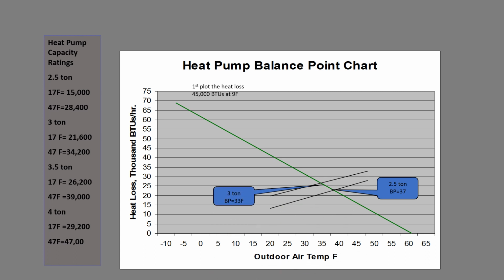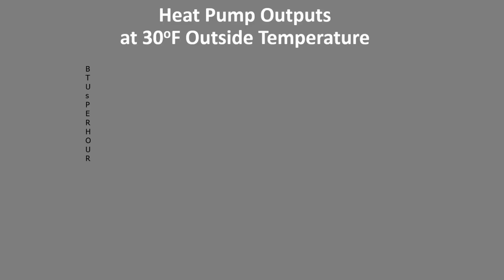Let's see what a 3-ton comes in. 3-ton comes nicely in at 33 degrees. Let's see what a 3.5 will give us. 3.5 down to 28. That would make it a really good choice for the PTCS program. Sure, we could go larger, we could go 4 tons, but you know, it's going to cost more money. It might not add that much economic benefit, and the ducts probably aren't big enough to handle that much air.